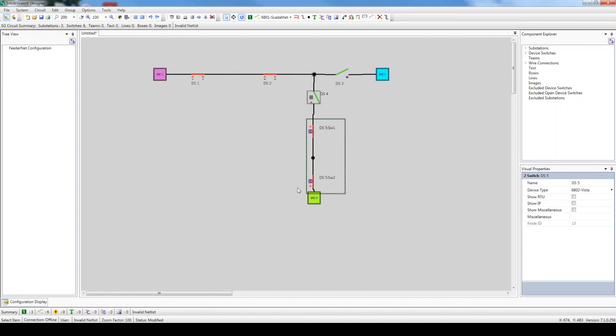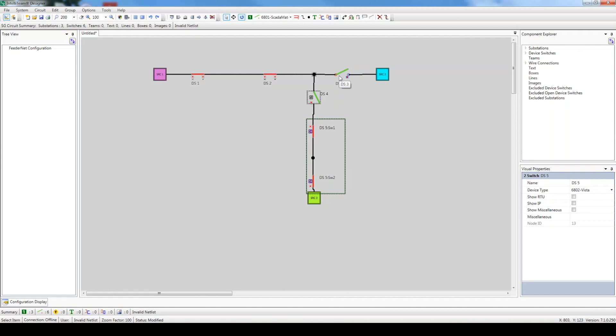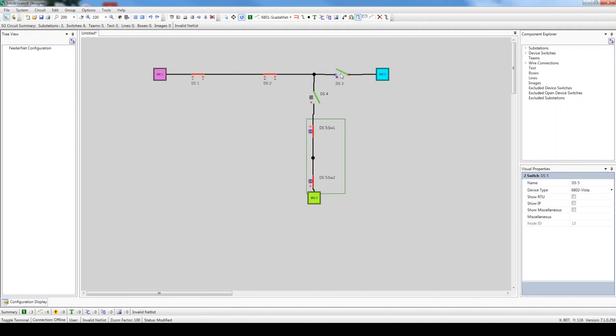For normally open devices, it usually doesn't matter where you place the switch terminals unless the switch is a tie sub, meaning it's the first switch after a substation source, which is the case with this IntelliNode switch. In this situation, the sensor side terminal needs to face the alternate source, or source 2, which is the case in our circuit. If this wasn't the case, the terminals can be flipped by clicking the Toggle Terminals button and then selecting the desired switch. Click it again to flip it back.